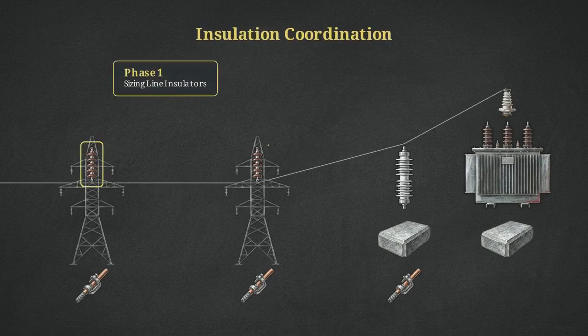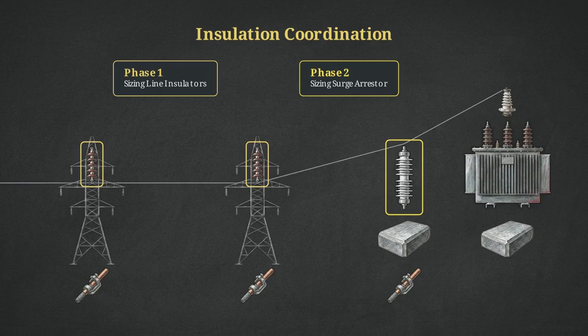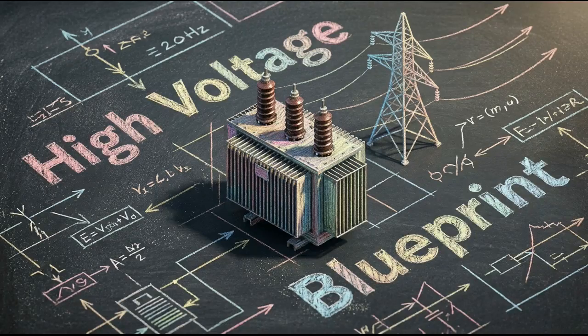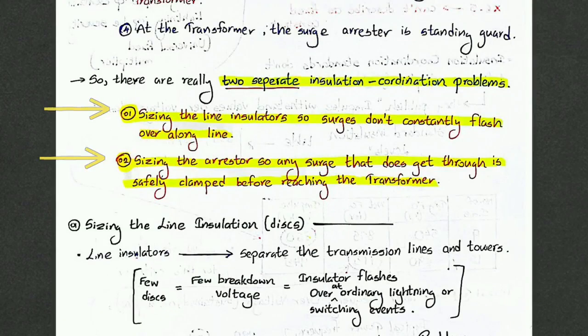First, line insulators are sized to prevent constant flashover faults along the towers. Second, the surge arrestor is calibrated to clamp any remaining spike before it reaches the transformer. Today, we are going to build a complete insulation coordination plan for a 220 kilovolt system from scratch. Designing these systems requires isolating these two protective layers and calculating their distinct tolerances against physical stress.